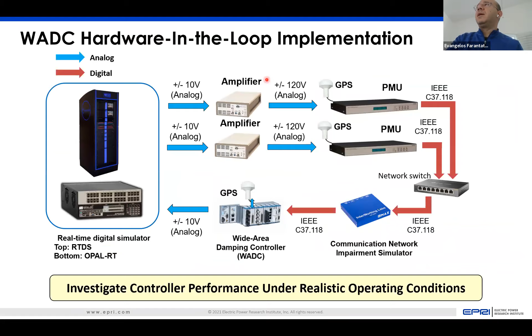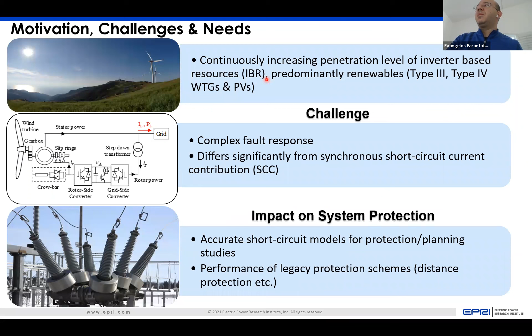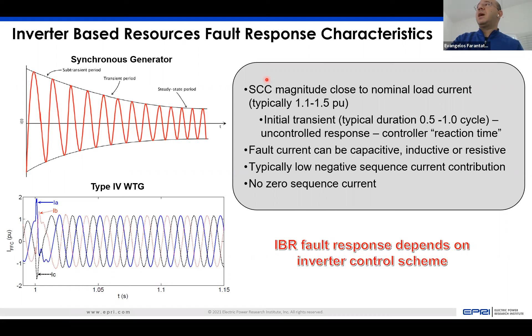I'll skip those. The last one I wanted to touch upon is protection. That's another area with a lot of challenges. The motivation is that inverter-based resources have a totally different fault response compared to synchronous machines, and the fault current they provide is very small compared to a traditional generator. So we have to rethink and redesign the protection system.